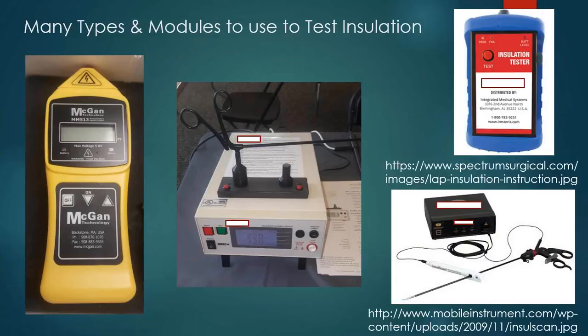Also, the insulation tester might need PMs or some type of preventive maintenance, like a yearly calibration. Does the tester need to be sent back to the vendor for this maintenance, or to your hospital's biomedical department? That's something you'd have to investigate. And if it's sent out and that's your only one, do they provide a loaner? Something else to ask.